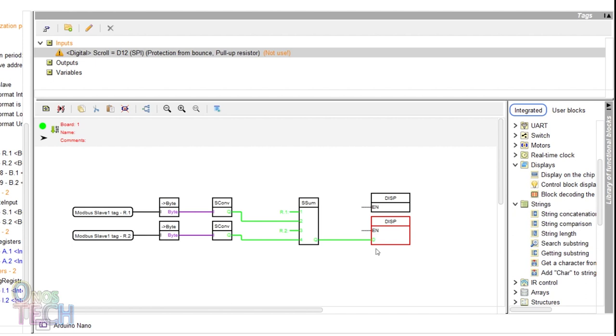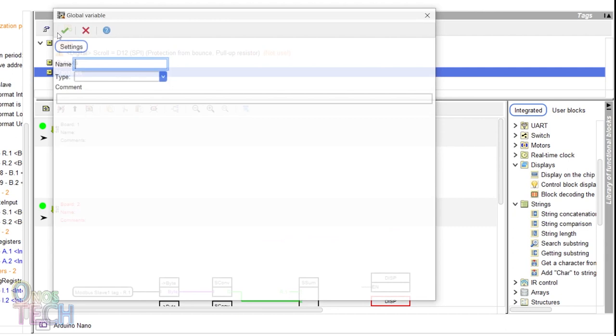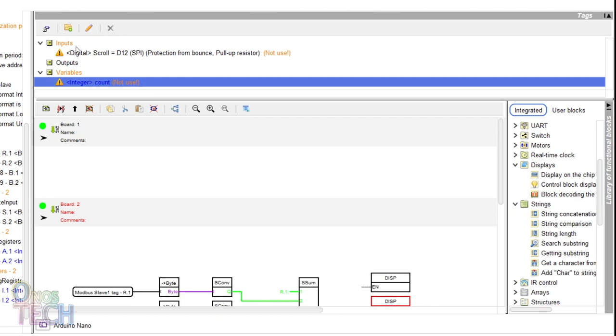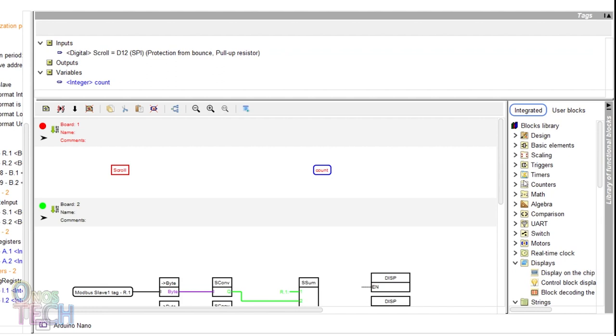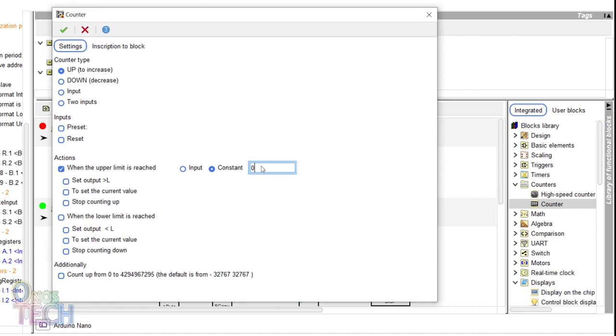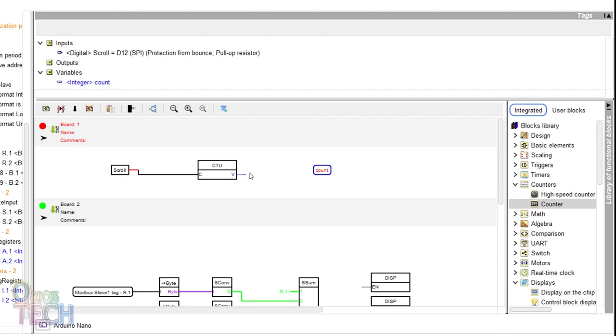To scroll through the other Modbus registers, add a board above. Create an integer variable tag called count and drag it and the digital input tag to the program. Drag a counter block into the program and configure it as an up counter with an upper limit of 6 to start counting from 1 again.